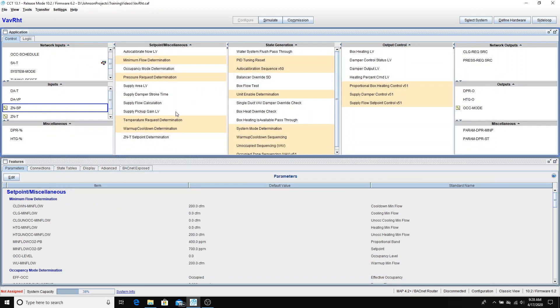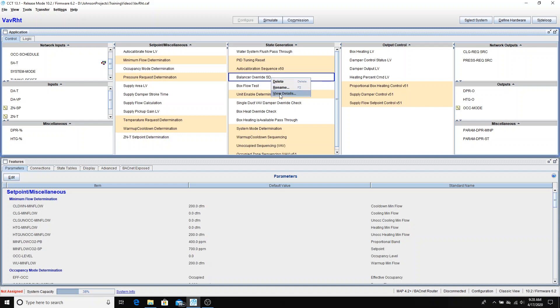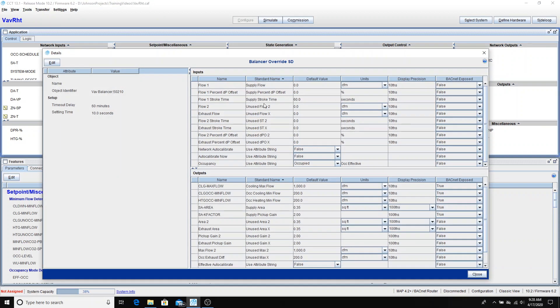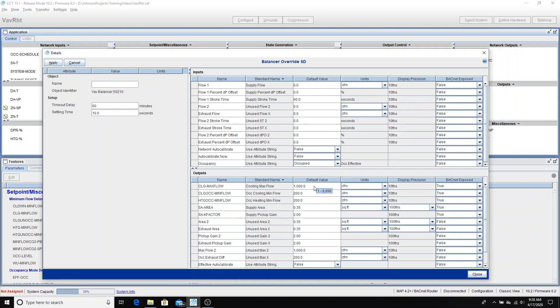The next thing that we need to do is put in our box size along with the min and max airflow settings. So that would normally come off of your VAV schedule. So we'll go into the balancer override SD block. That's where all that information is located. And I'm going to go into edit mode. And on my inputs. I'm sorry, on my outputs, rather.